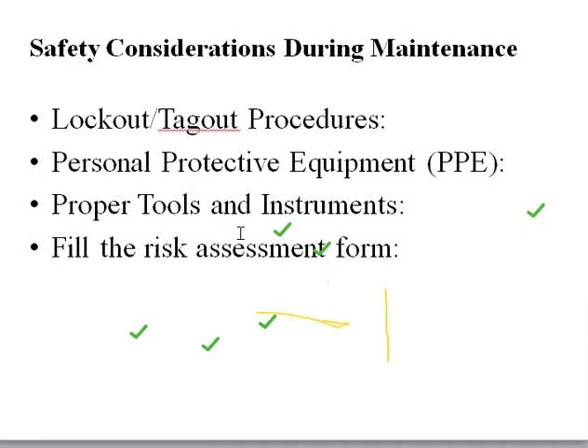Use of multimeters, insulation testers. Like if you use a screwdriver to test if power is there, that is the wrong tool. You may be electrocuted within a minute, very fast. Also we fill the risk assessment form before doing any maintenance. Doing any maintenance without a risk assessment form is prohibited here in our factory. You have to always get the risk assessment form and assess any possible risks that are likely to occur and look for the solutions. What are the solutions to those risks? If they are all matching and there are no possible risks, then you proceed to the maintenance.